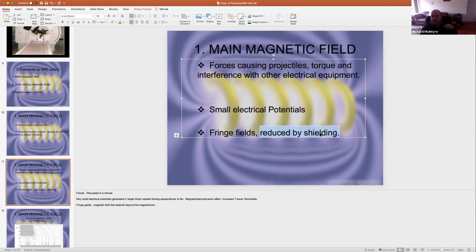So we have processes called shielding, and that shielding is designed to do a couple of things, but mainly to tighten that magnetic field to keep it within the magnet. Also, the shielding helps keep that magnetic field as homogeneous as possible inside the bore, at the isocenter of the magnet. That's where we're scanning. We don't want any changes in that magnetic field. It's got to be completely 3 Tesla inside that small area, about the size of a basketball, at the isocenter of the magnet.